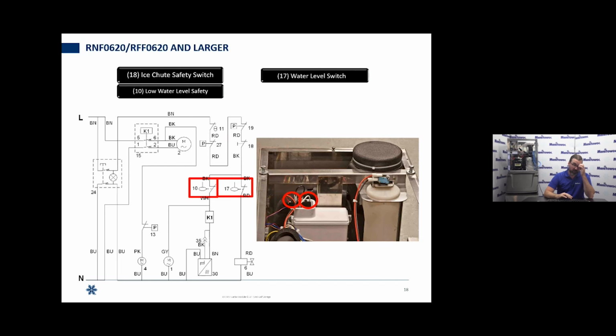Then we're going to have our low water safety. Now, of course, low water safety will cut us out. We also have our water level switch. Now, the water level switch is not going to prevent us from starting if we have a failure with that switch itself. We probably will eventually, because we're going to run out of water more than likely, and that'll trip our low water safety. But that water level switch really isn't a safety in this scenario. That's just controlling the water inlet valve, telling it when to turn on and off. So it's part of the control system, but it's not what I would consider a safety in this scenario.